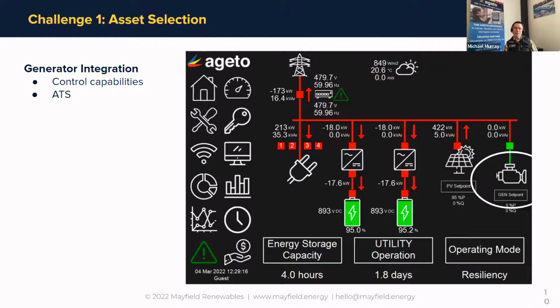So the terminology between the solar plus storage space and the generator space is very different. I used to work in the generator space, so we have a lot of experience with that. For energy storage, it's grid forming or grid following. With generators, it's isochronous, which is grid forming, or base load, which is grid following. Also, sometimes base load, which is a generator term, is called demand response mode. So there are a few different terms, but basically you want the generator to be able to ramp up in parallel with an energy source and connect to it while it's running. Base load is the most common term, and that's desirable.